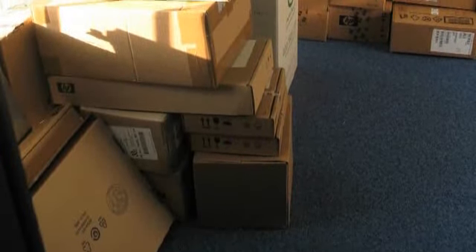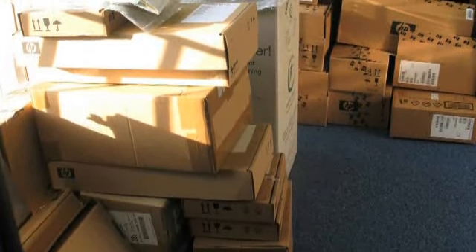That may not be by touching anything to do with the power infrastructure, but by doing something else. A good example is where we did an audit in a university and they had a pile of cardboard boxes in the corner. Now, cardboard's bad for data centres because it creates dust. Dust clogs fans, fans work harder, they get hotter, we need more cooling, therefore more power. So we said to them, look, take the boxes out of the data centre and you're actually going to save money. They did that and saved around 3% on their power bills.